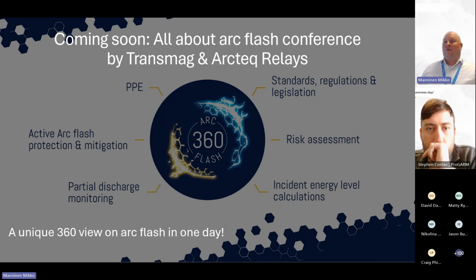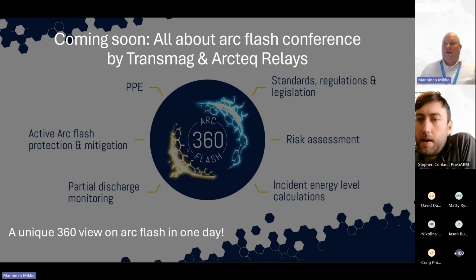New build installations, of course, are practically standard already. Every low voltage panel here in Finland, for example, and every medium voltage panel does have arc flash protection as a standard. But the retrofit installation is actually very big. For example, if you have 40 year old switchgear and you do good maintenance for the circuit breakers, it is a good addition to add more safety, like additional safety on the equipment.